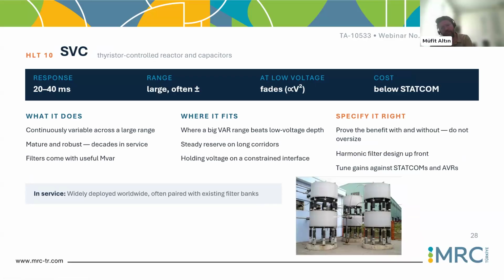SVCs, you can think of as the older version of the STATCOMs. It is a thyristor controlled reactor, and the impedance that you have could be a reactor or a capacitor. They are slow, maybe more than 20, 40 milliseconds, most of them starting around 100 milliseconds.